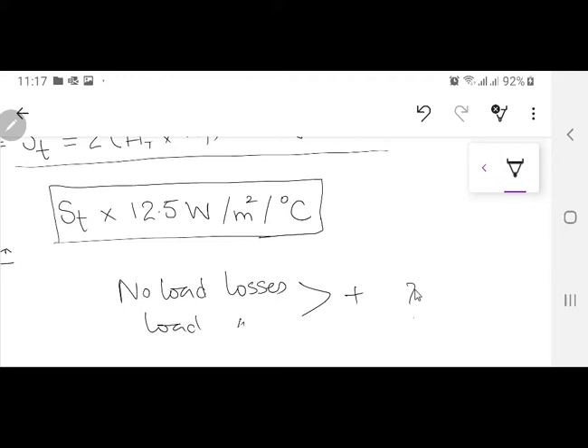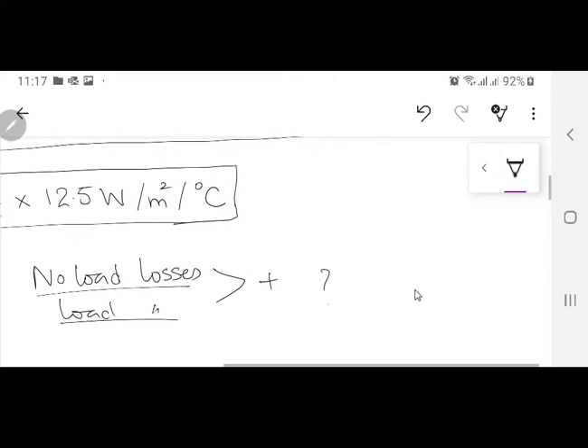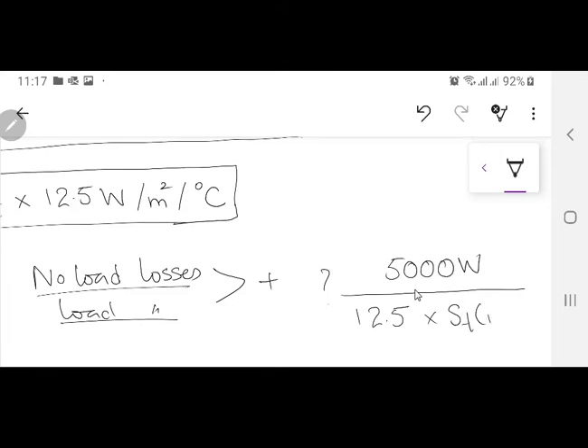I am repeating: suppose no load losses plus load losses comes out to, for example, 5000 watts. That 5000 watts divided by 12.5, multiplied by ST, certainly in meter square - this is very important, not millimeter square, in meter square.